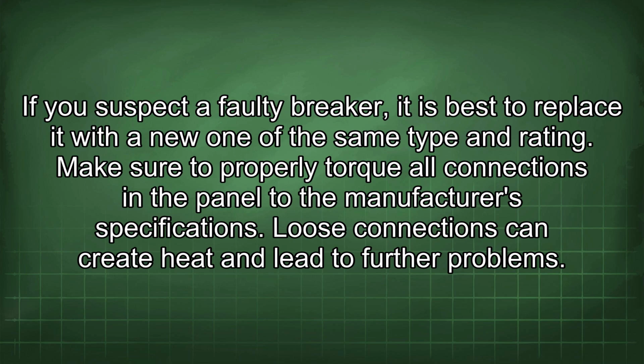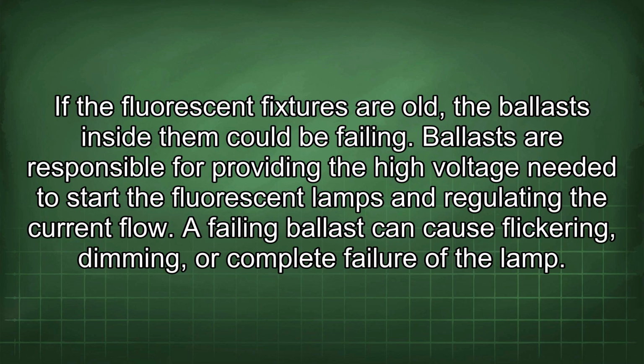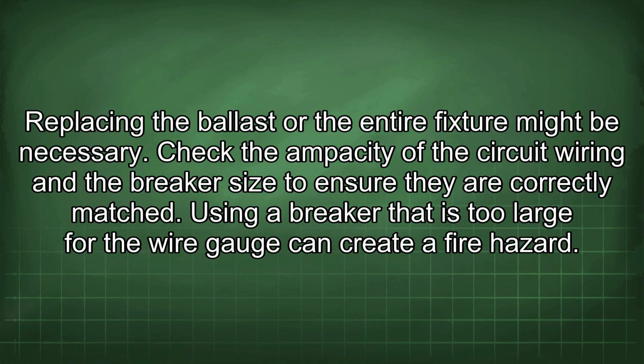If you suspect a faulty breaker, it is best to replace it with a new one of the same type and rating. Make sure to properly torque all connections in the panel to the manufacturer's specifications. Loose connections can create heat and lead to further problems. If the fluorescent fixtures are old, the ballasts inside them could be failing. Ballasts are responsible for providing the high voltage needed to start the fluorescent lamps and regulating the current flow. A failing ballast can cause flickering, dimming, or complete failure of the lamp. Replacing the ballast or the entire fixture might be necessary.